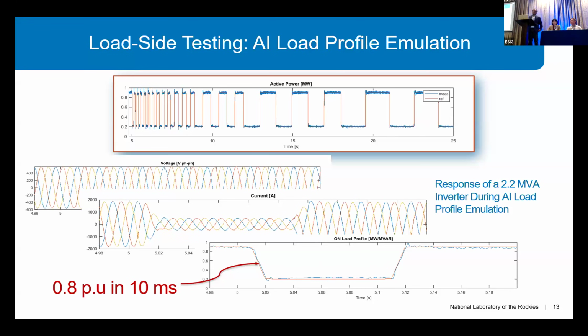So the first unique test that is required for data center power supply equipment is emulating an AI load profile. And what you see here is we use one of our grid simulators to act as a load. Instead of a grid emulator, it basically became a load emulator, and it can act as a data center load, where it can emulate any AI load profile that we feed into it. On the top, the orange one is a reference, and the blue one is the actual measurement.